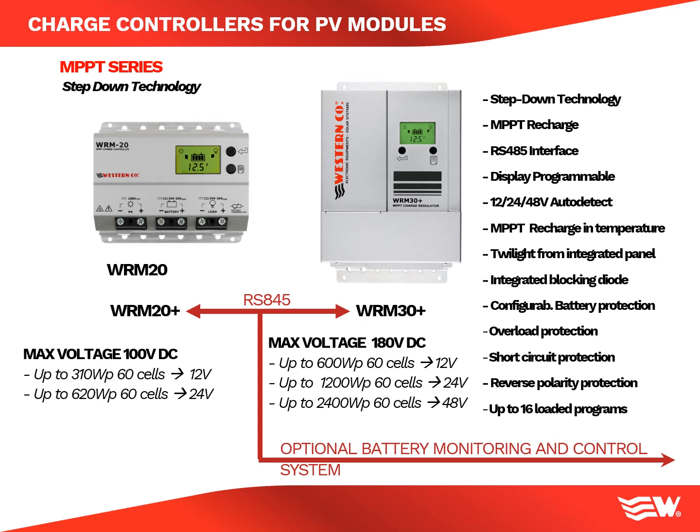WRM30+ has been properly designed for industrial applications such as power supplying for TV radio relays, road signs, or wall houses completely standalone. A special feature of this product is the presence of two separate charging channels and therefore a double input for PV modules. This allows the management of two independent strings, for example if they are composed of modules of different features, or exposed on two slopes. With identical strings, channels can be paralleled, thus optimizing the efficiency.